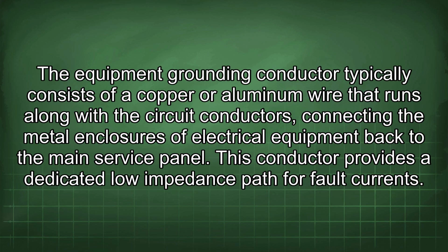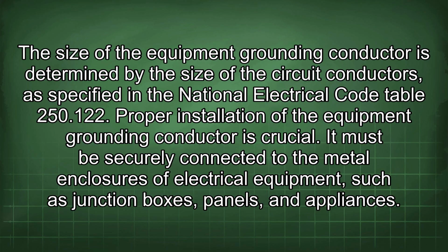The equipment grounding conductor typically consists of copper or aluminum wire that runs along with the circuit conductors, connecting the metal enclosures of electrical equipment back to the main service panel. This conductor provides a dedicated low impedance path for fault currents. The size of the equipment grounding conductor is determined by the size of the circuit conductors, as specified in the National Electrical Code Table 250.122. Proper installation of the equipment grounding conductor is crucial.